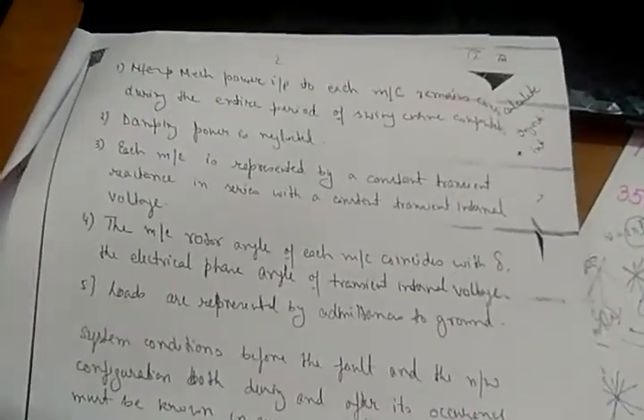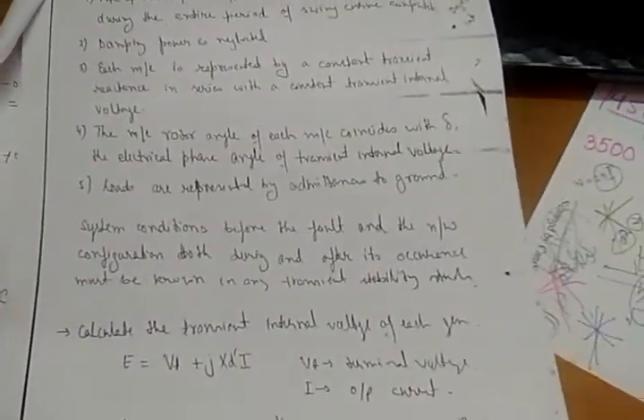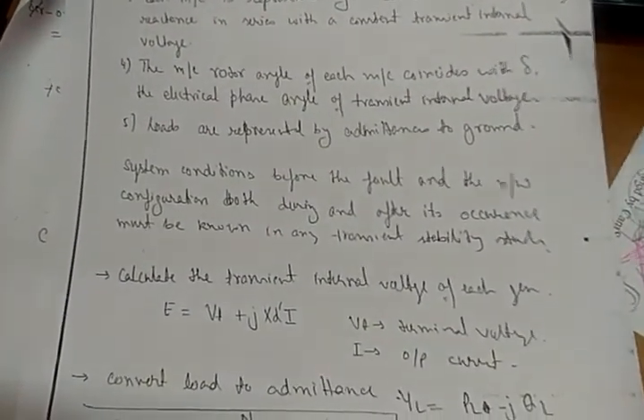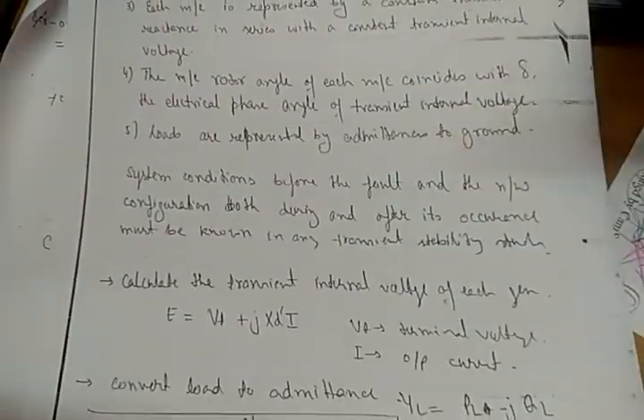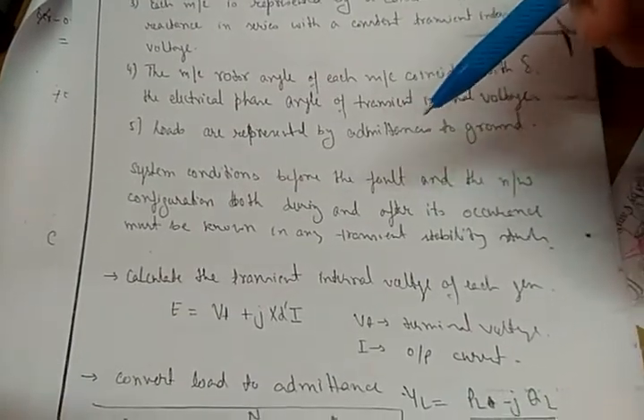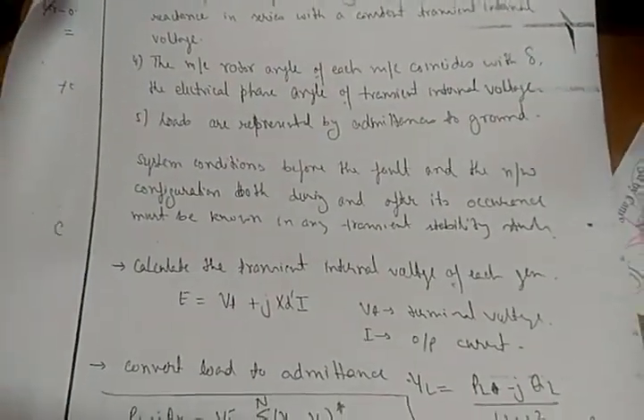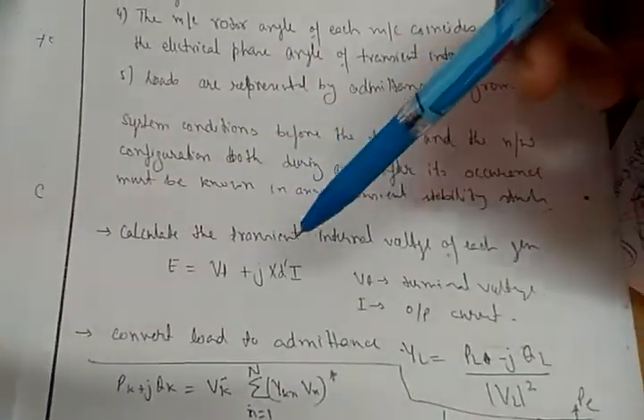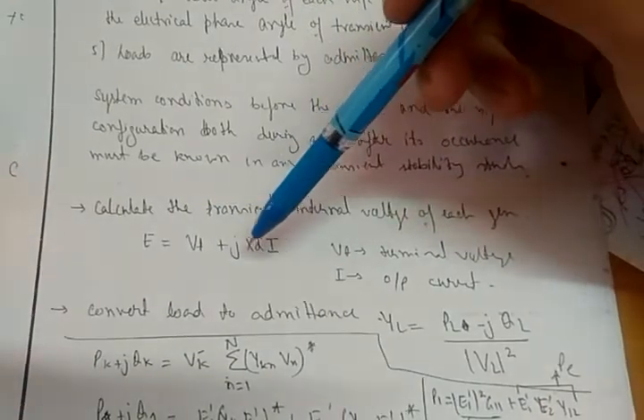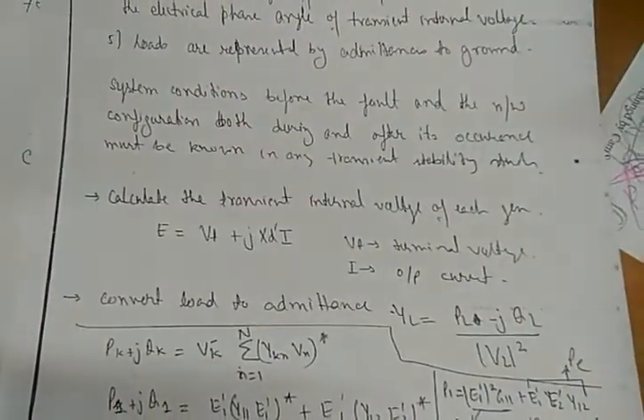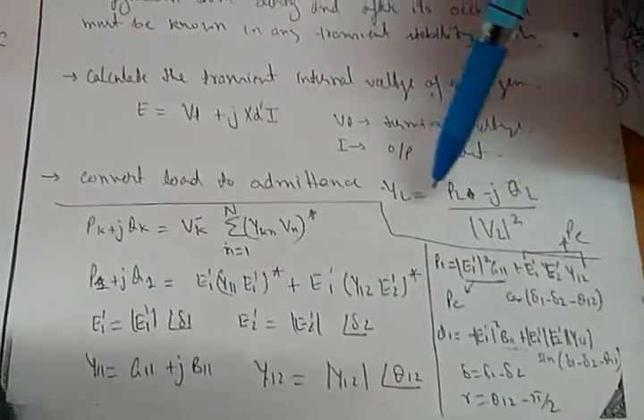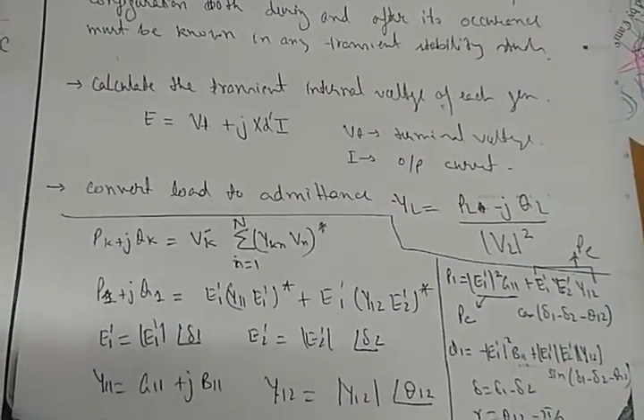Okay. Now, for transient stability analysis, we should know what the system configuration is before fault, meaning under normal condition, during fault, and after fault. Because if the system configuration changes, it will change the admittance matrix Y of the system. Okay, so the system conditions before fault and the network configuration both during and after the occurrence of the fault must be known in any transient stability study. Then we calculate the transient internal voltage of each machine similarly, using the formula VT plus J times XD into I, where VT is the terminal voltage and I is the output current. And how do you convert the load into admittance? Y is equal to P minus JQ by V square.